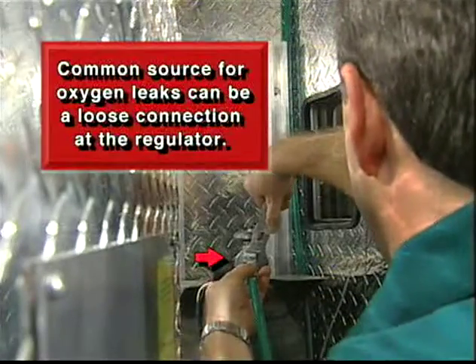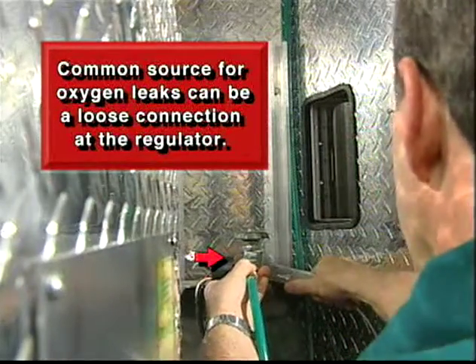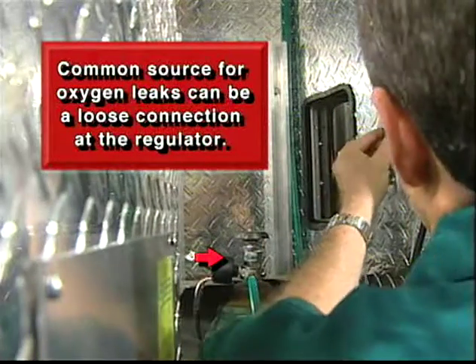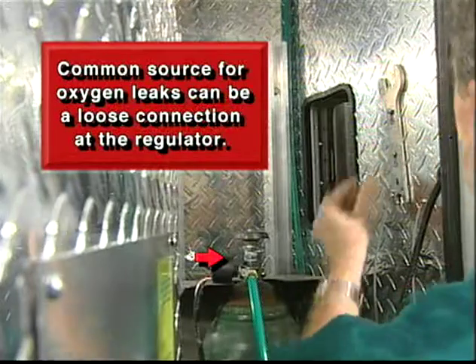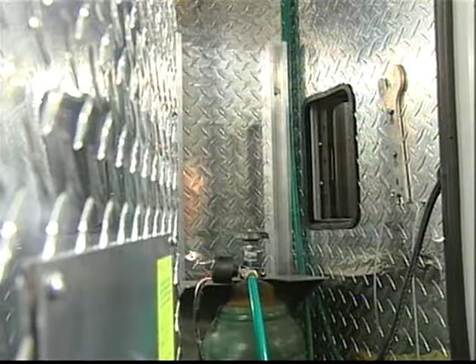A pressure regulator is installed on the top of the main oxygen supply tank. An oxygen tool is fastened to the compartment wall to aid in the changing of your oxygen tank. A pressure test is performed on every ambulance before and after the system is installed. Whenever you change oxygen tanks or disconnect fittings, you should spray the area with diluted dishwashing soap and watch for bubbles. If bubbles form, retighten your fittings and repeat this procedure until no bubbles are present.